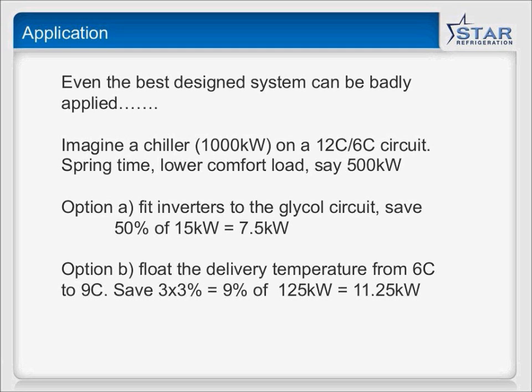So raising the evaporating condition of this plant, so that the glycol is going out at 9 degrees instead of 6 degrees, will make a 9% difference in energy consumption. Now, the motor on the chiller is likely to be far bigger than the motor for the glycol pump, so 9% of 125 is an 11.25 kilowatt saving.